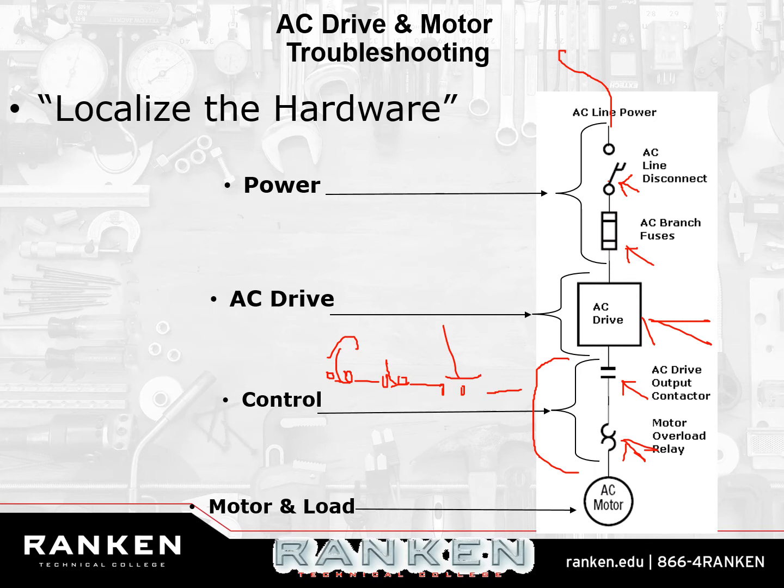Not necessarily controlling the overload, but as part of the overload circuit and as part of the control circuit for our push buttons, our toggle switches, our whatever the case may be, our automation controls. So if you have a problem with things down here, you might be having a problem with your automation system. You might have a bad photo eye. You might have a bad prox switch that's not letting it go.